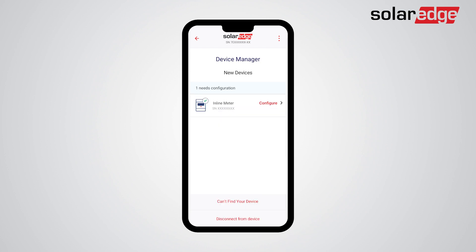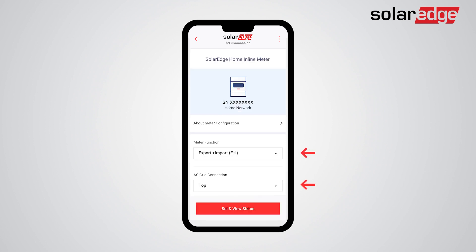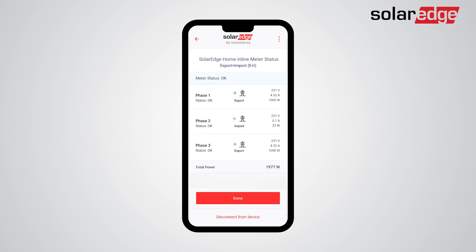Now we configure the SolarEdge Home Inline Meter — tap Configure. Note that the default meter function and AC grid connection are Export/Import and Top respectively. In case you need to change parameters, select the drop-down menu to select the desired configuration. Note that meter function and AC grid connection should reflect the physical wiring and position of the meter in the electrical cabinet. Tap Set and View Status.